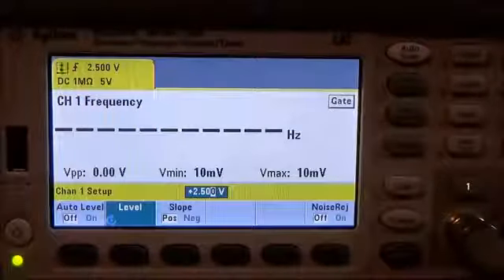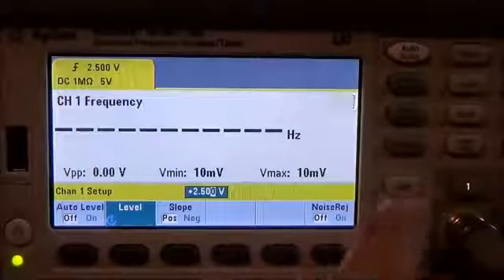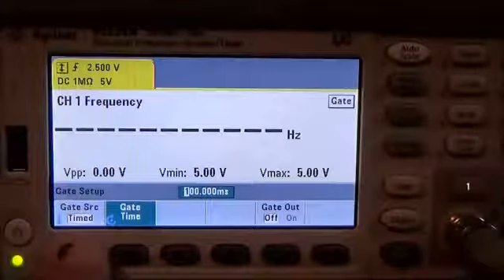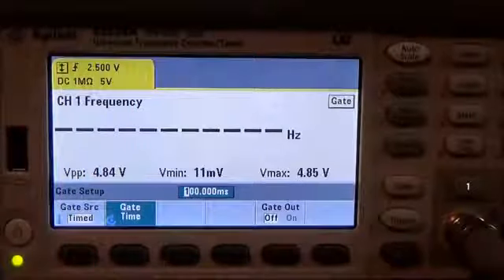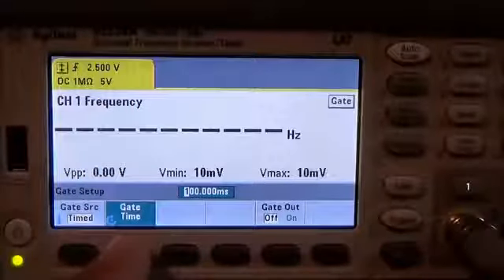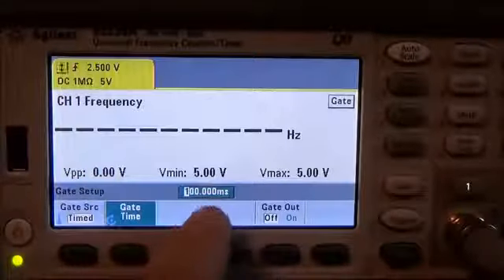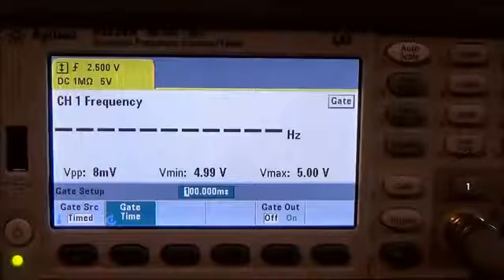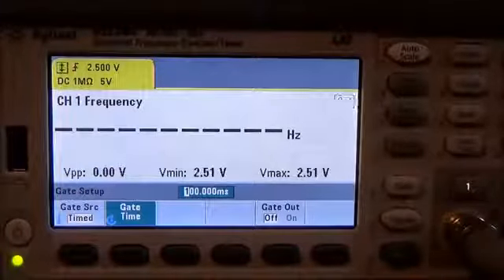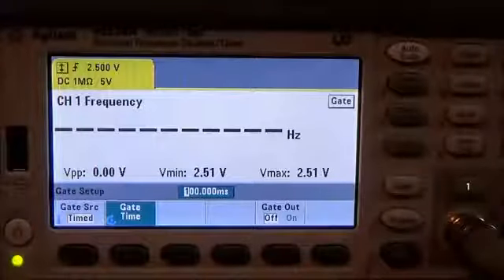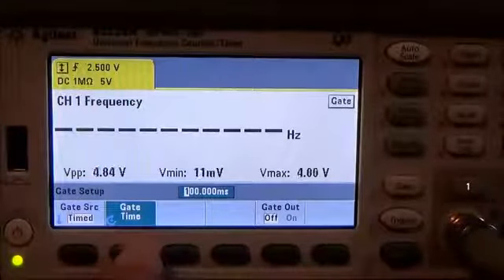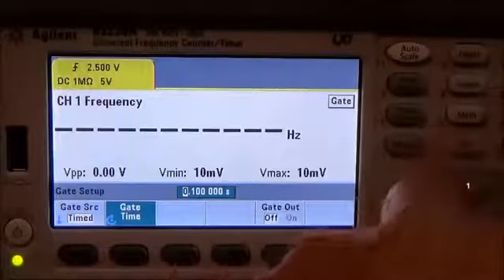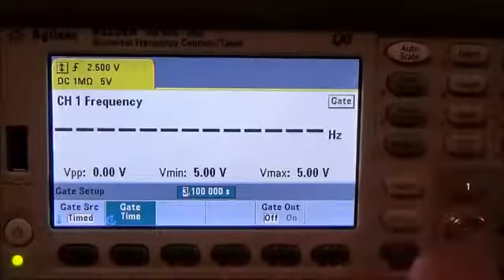The third hint I want to pass along is gate time. So let's press the gate button and then notice that the gate source is time. This is normal by default but if you notice the gate time is currently set to 100 milliseconds. Well if you think about this we've got a signal that is one cycle per second so we want to set the gate time a little longer. So we can do that by pressing the gate time soft key and then going ahead and increasing the number of seconds to maybe three.